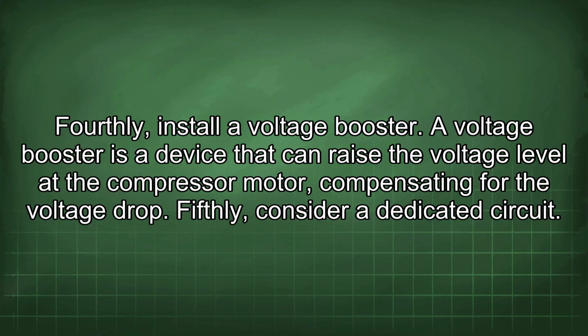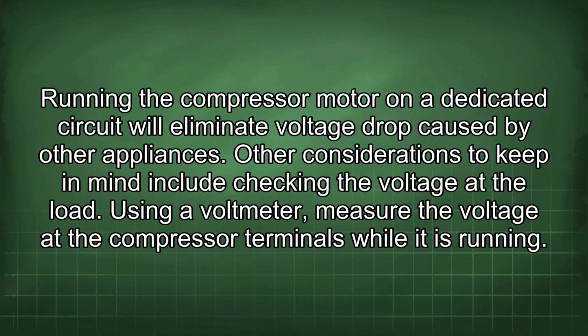Fourthly, install a voltage booster. A voltage booster is a device that can raise the voltage level of the compressor motor, compensating for the voltage drop. Fifthly, consider a dedicated circuit. Running the compressor motor on a dedicated circuit will eliminate voltage drop caused by other appliances.